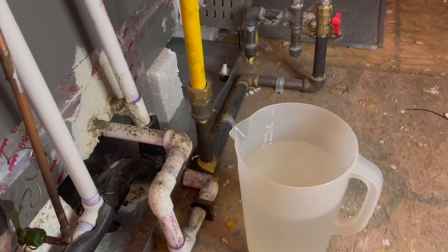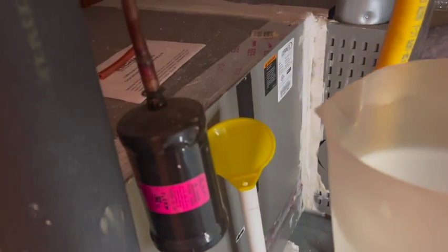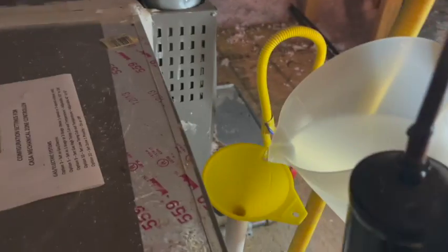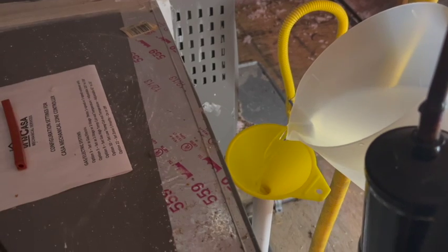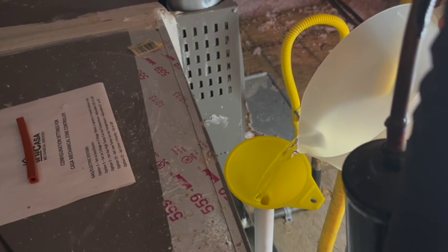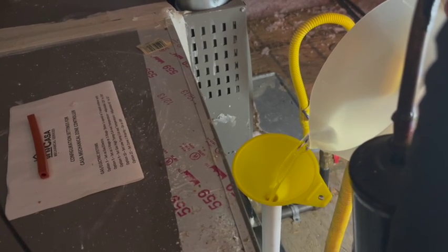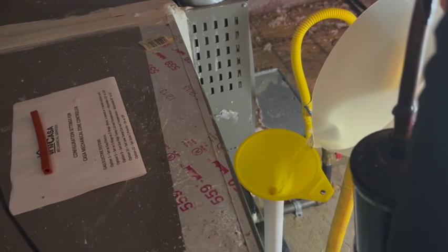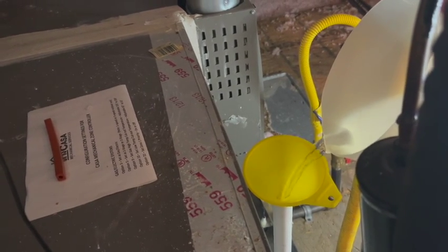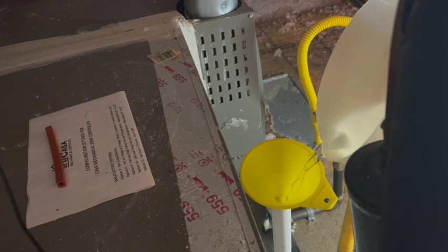All right, now that we've had time for the bleach solution to soak in, do its thing, we're going to go ahead and flush the primary. So we're just going to do that by just pouring this gallon in the funnel, flushing that line out, so you don't worry about anything clogging up. Again, you go real slow to make sure it doesn't overflow and spill out. This water should be warm, it doesn't have to be hot, but it should be warm just to help push out any debris that was in the line.